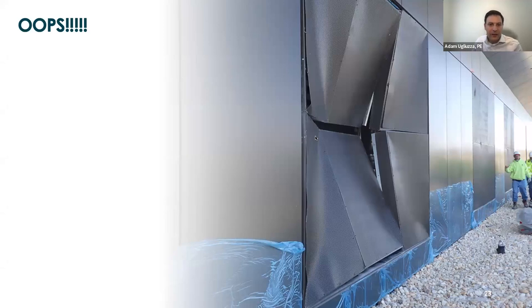Here's an example of what happens, and why the testing agency shouldn't be doing the prep. It's the mechanical contractor's and GC's responsibility, because you can damage equipment if it's not shut off properly. This was an open air plenum. They had not shut the units down. Instead of sealing at the interior line, where the dampers are, as I showed in the previous picture, they were sealing the louvers on the outside. They got to the last louver and sealed it up, and because the system was still on, it continued to pull air, created a suction, and actually collapsed the louver in on itself. So it wasn't a good day for them. I'm glad I wasn't responsible for it. Something to keep in mind. This is why the coordination is so important. You've got to have the right people there who understand the system so that you don't damage anything.